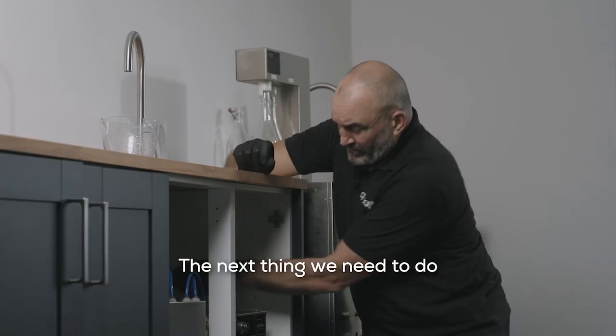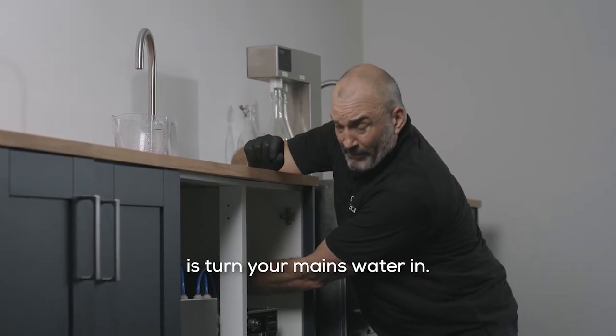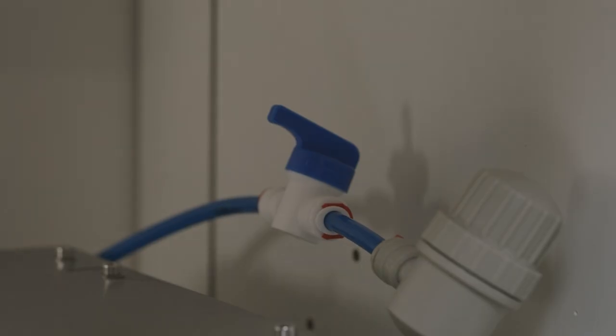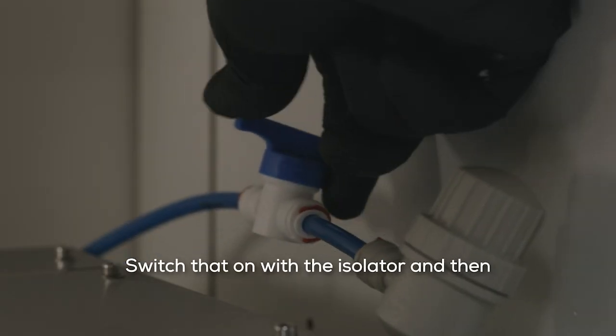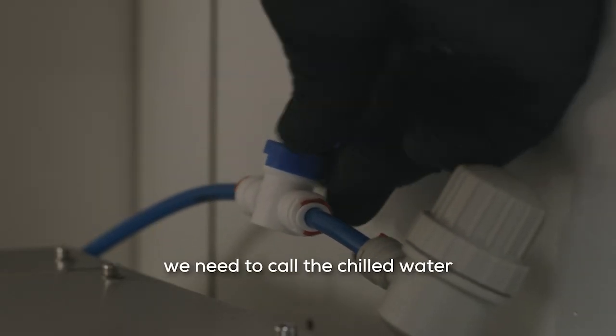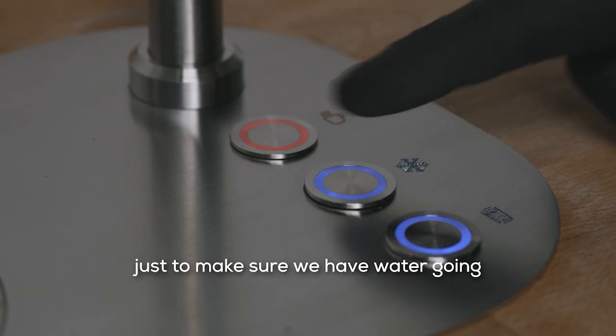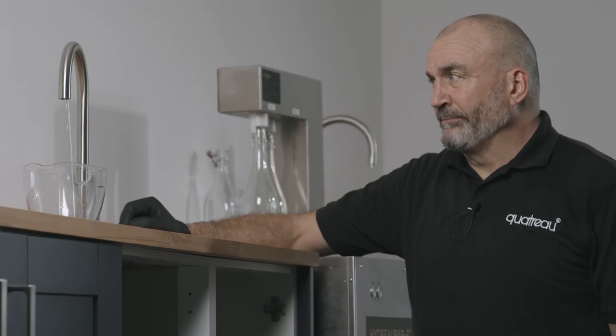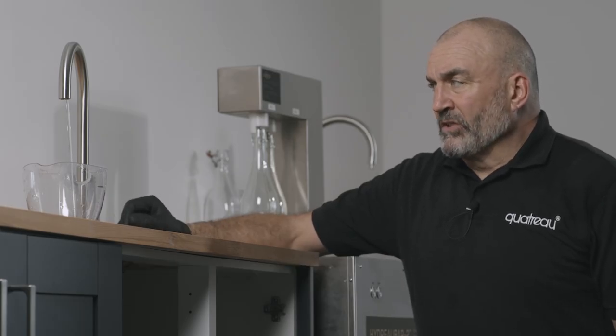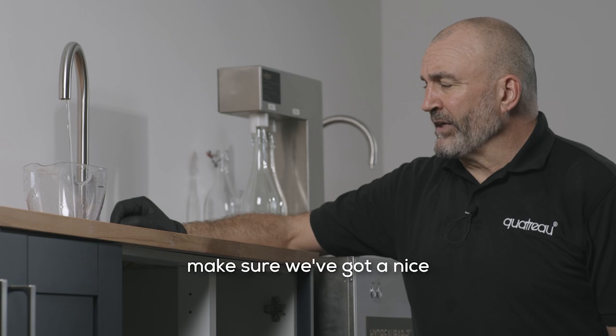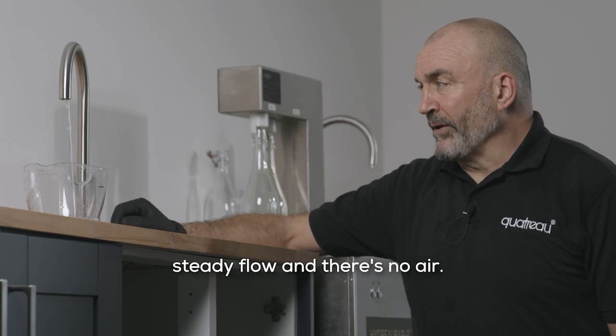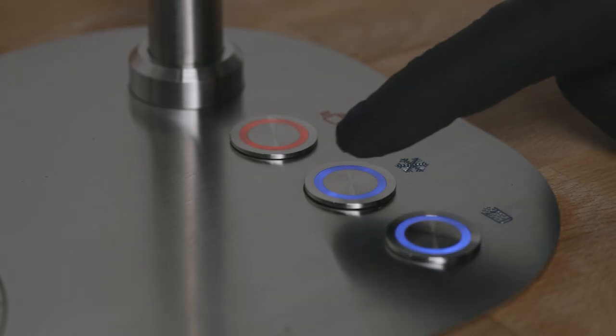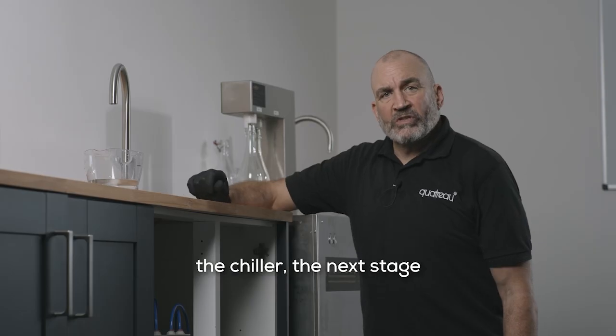The next thing we need to do is turn your mains water in, switch that on with the isolator, and then we need to cool the chilled water just to make sure we have water going through the chiller. Let's let that flow for a few seconds just to make sure we've got a nice steady flow and there's no air. Now we know we've got water going through the chiller.